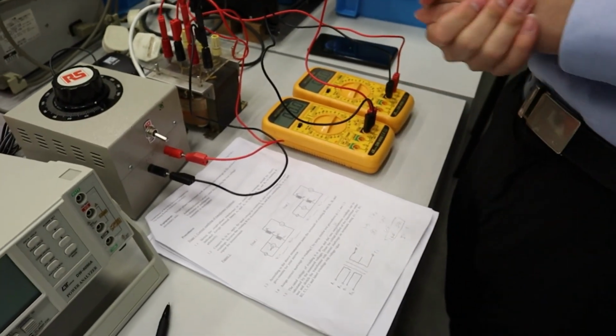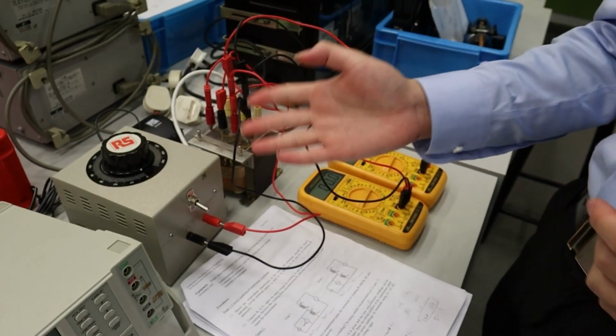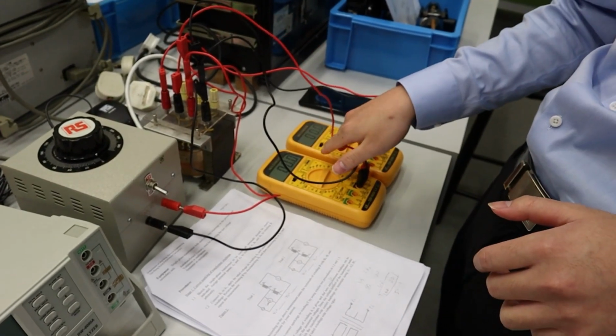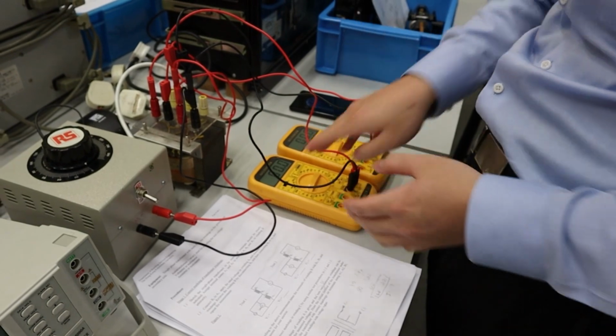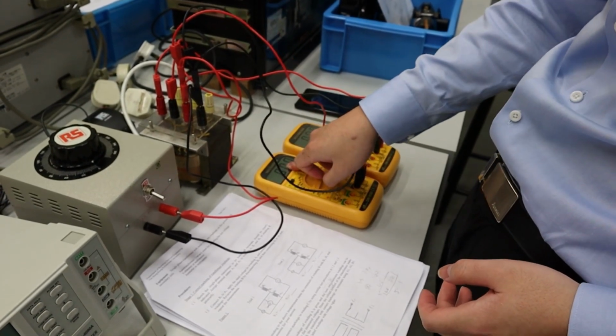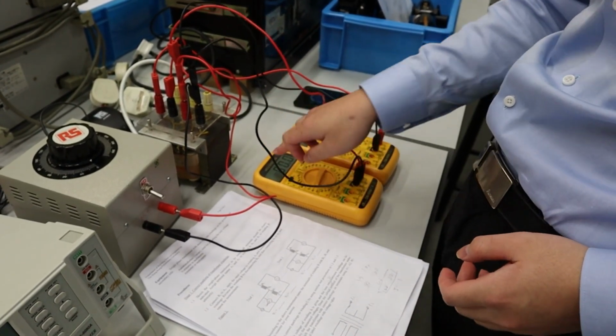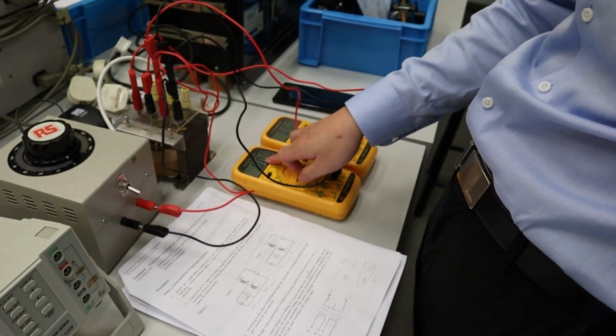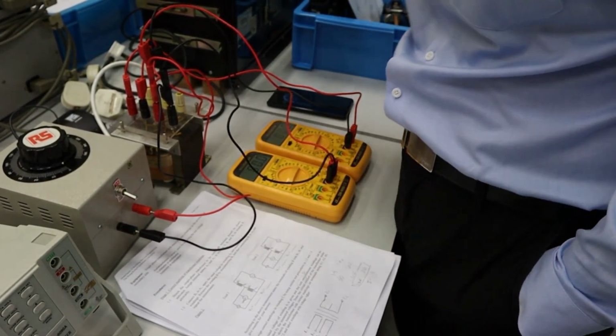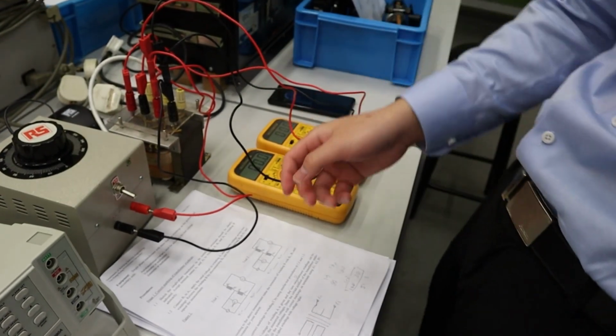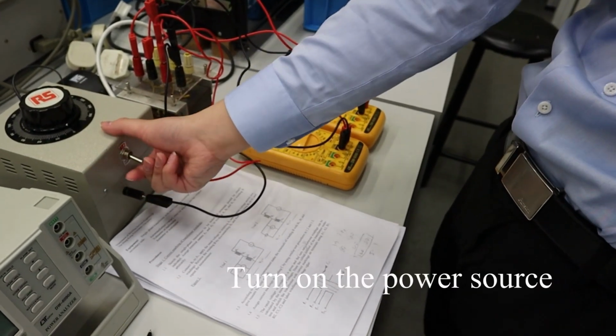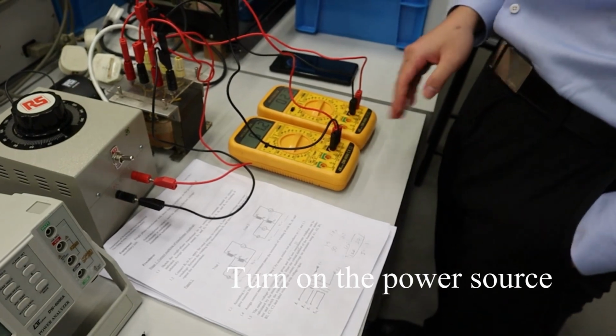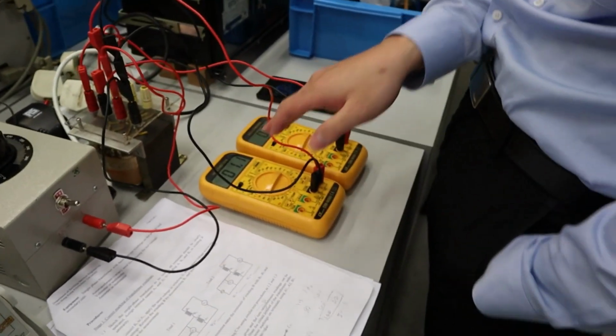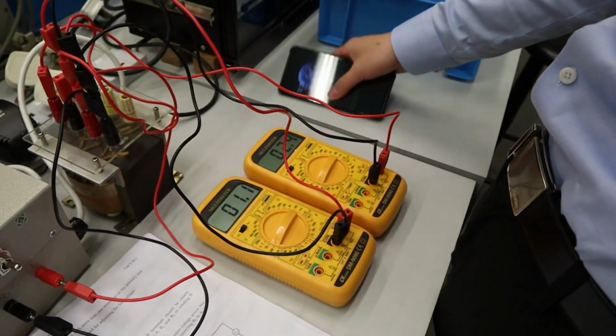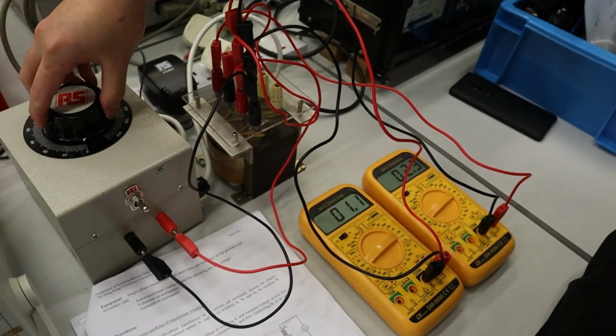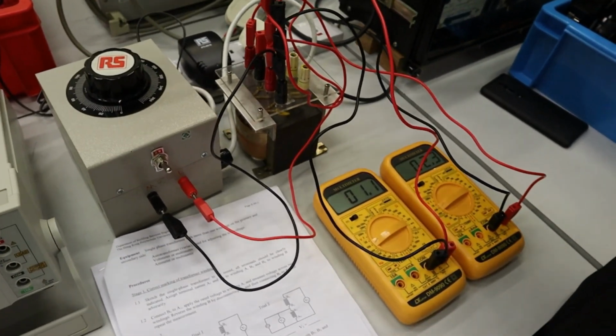Next step, we have to turn on the power source and see the change of these readings. We have to adjust the voltage on transformer A to 100 volts, because that's the rated voltage on transformer A. So we need to check - okay, the power source is turned on, and then we turn on the power source. Okay, we can see a little bit of readings here, please pay attention to the readings. We are going to adjust the power source to slowly increase the value.